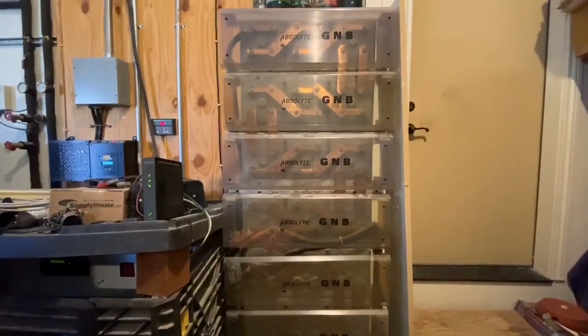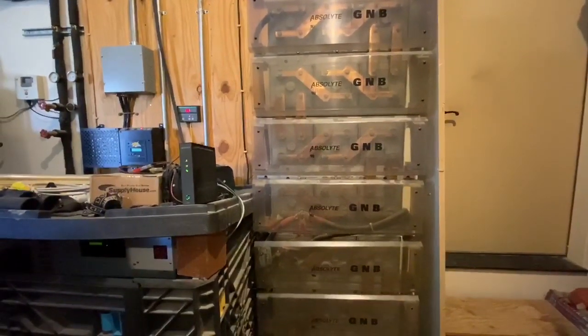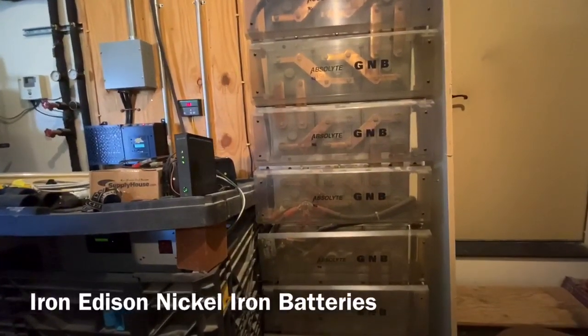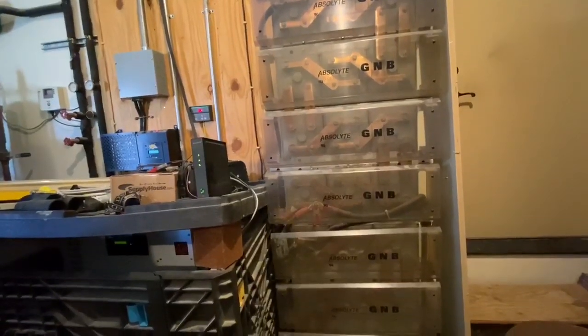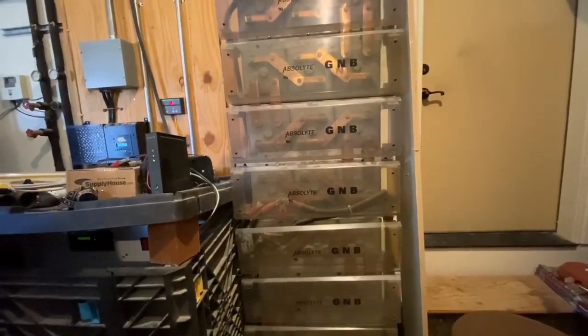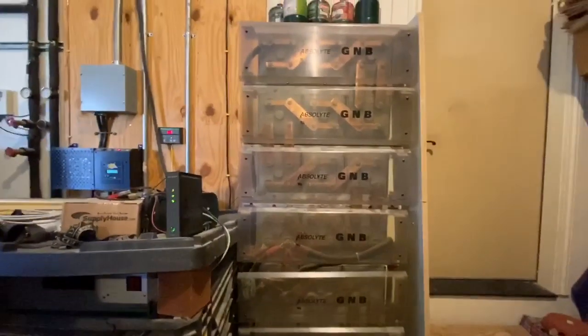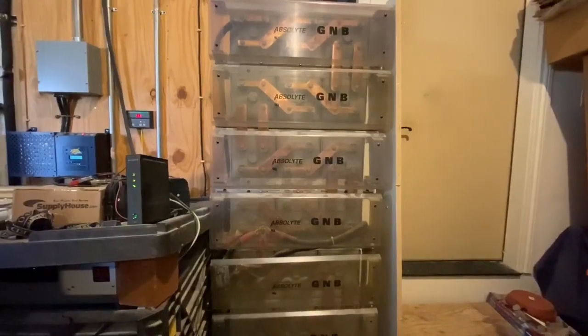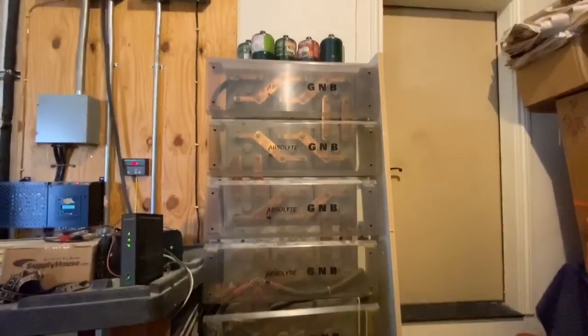And we are going to replace them with a different kind of battery. And I couldn't tell you without Brian's help, but it'd be a very different setup. And you don't add water to them or anything like that. The batteries we're going to get are not sealed and they will require maintenance. And the other issue is they off-gas. So we're going to have to build an enclosure for those and a rack system to put them in.